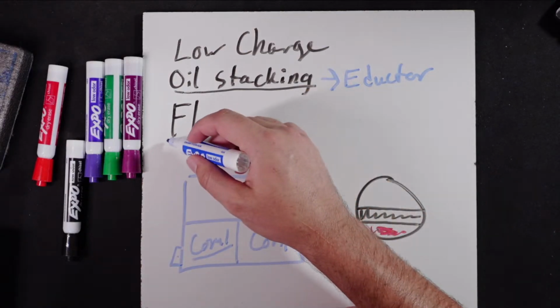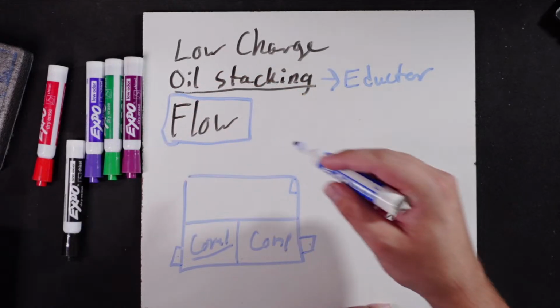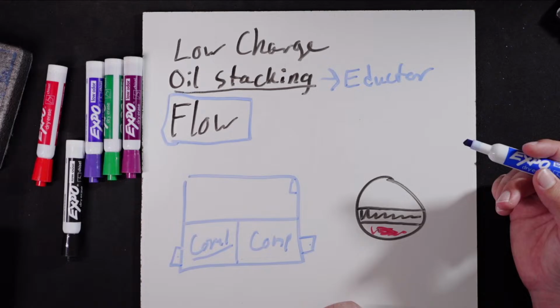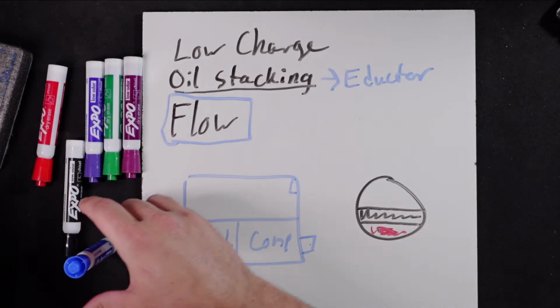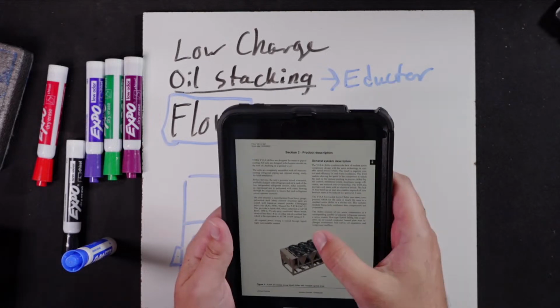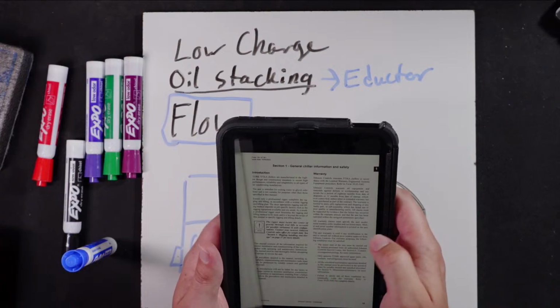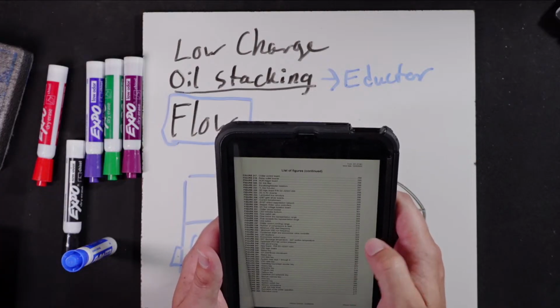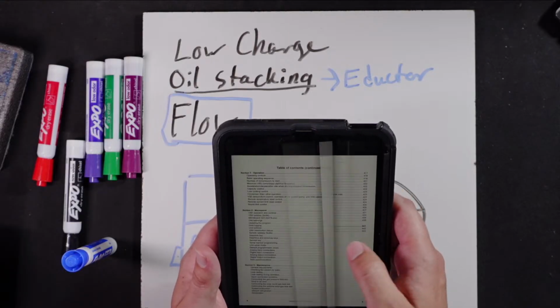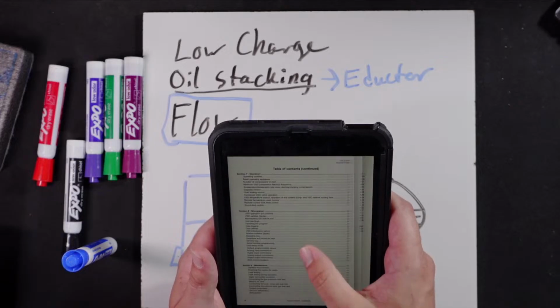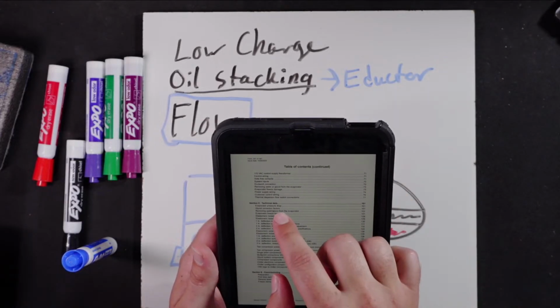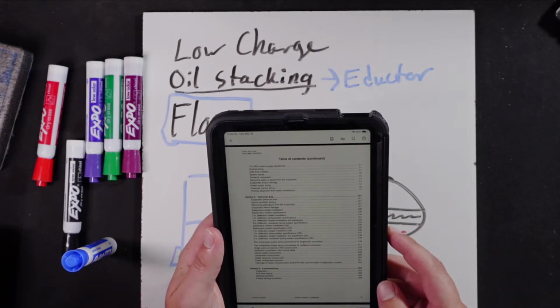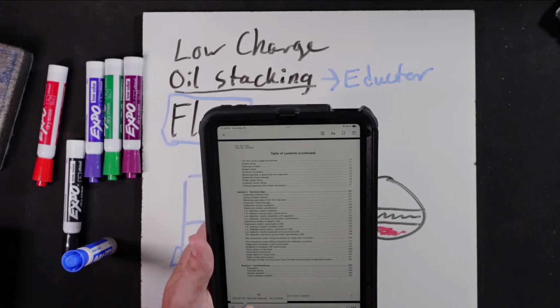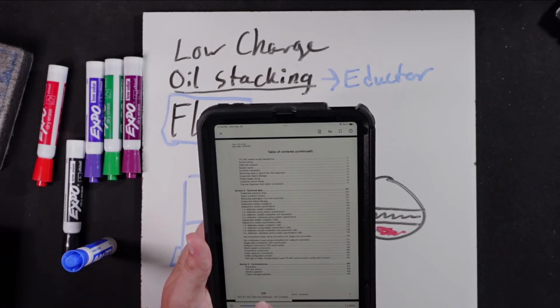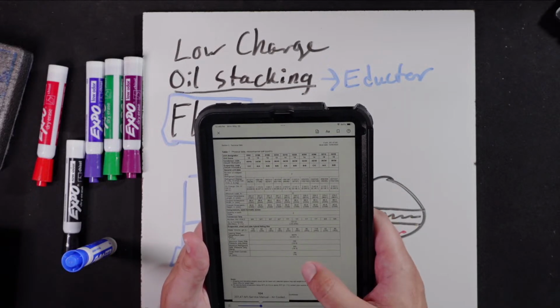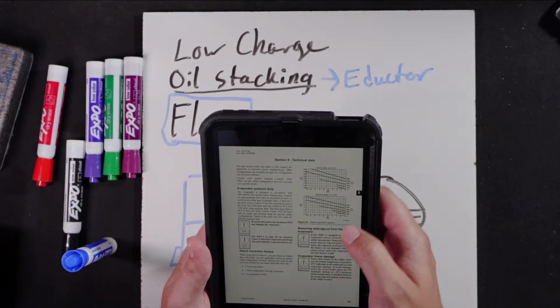That takes us to flow. It is far more likely, given what you've explained, that we don't have proper flow. And if memory serves, I'm pretty sure there's actually flow charts in this manual. Now, you may not have this manual. When I was reading through the table of contents, I'm quite confident: technical data, evaporator pressure drop is page 101. So let's go look at that real quick. Let's go to 101. Right about there. This is 103. 101. Here we go.